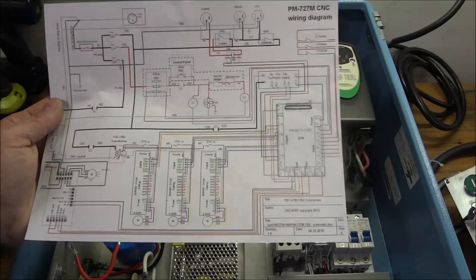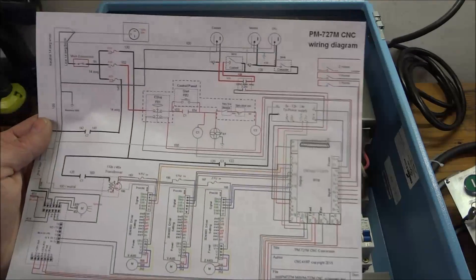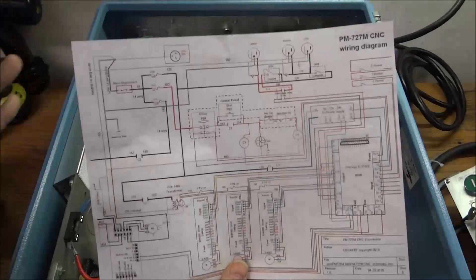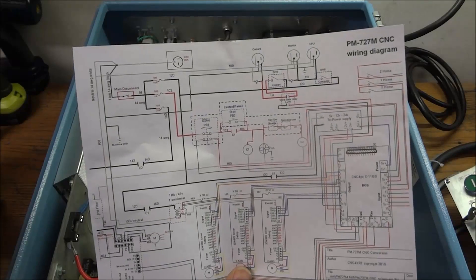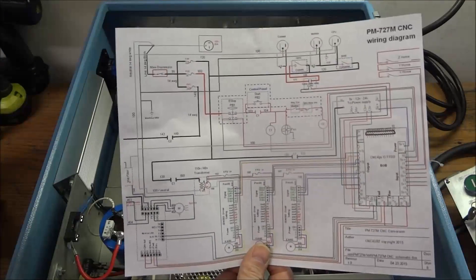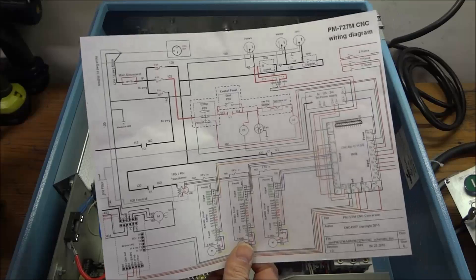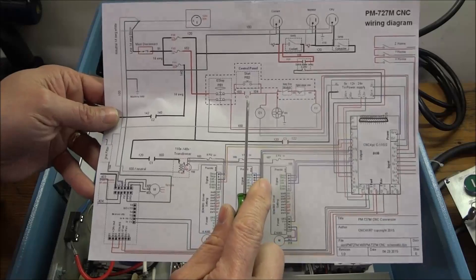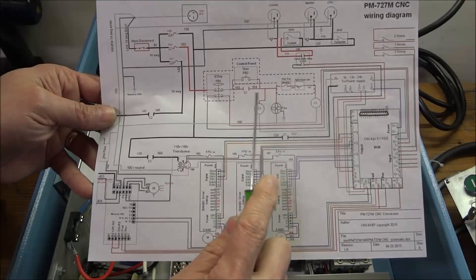You don't know where the equipment is and what stage it's in and you definitely don't want the spindle to start back up. You're going to either tear something up or injure yourself. So this is why the holding contact and holding circuit is needed.